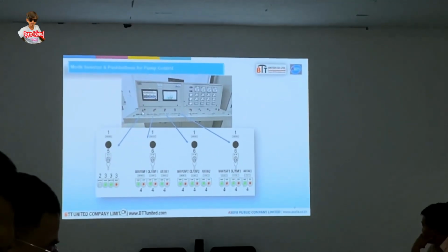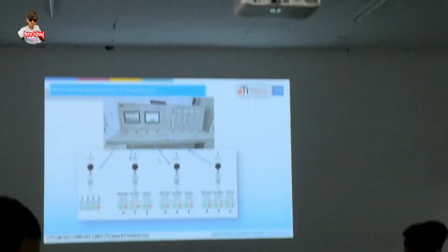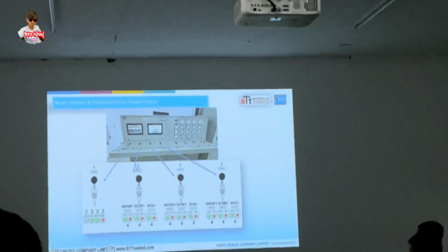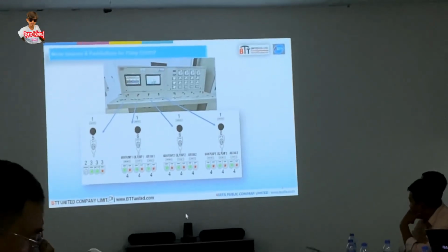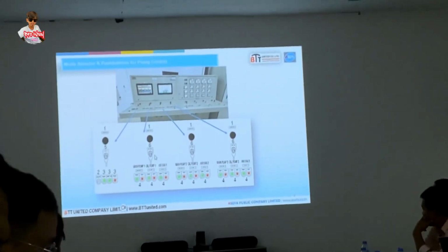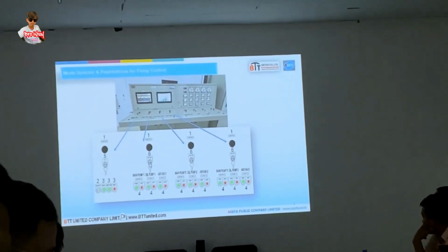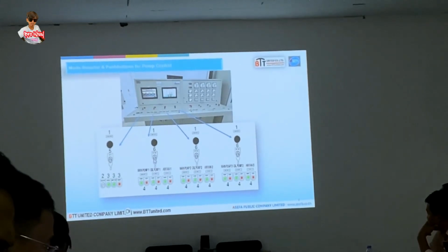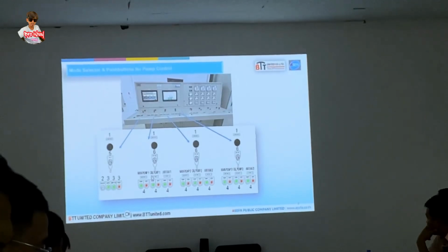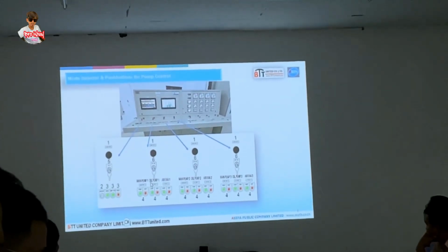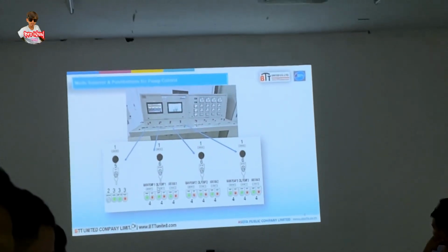But if you want to shut down only one particular system, maybe pump number 1, you shut it down by pressing this, number 2, number 3, and so on. The key selector, like I mentioned before, will have SD and CD, meaning SCADA or control desk. At this moment in time, we are only equipped with CD, which is the control desk control.